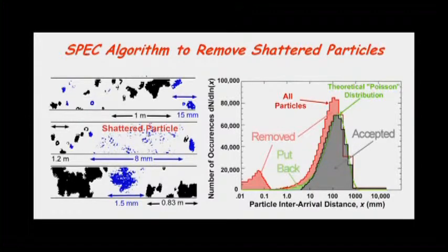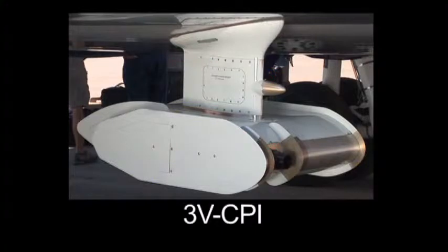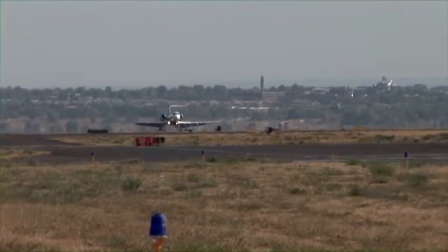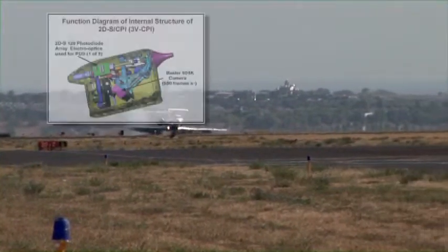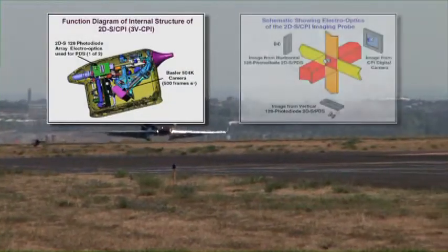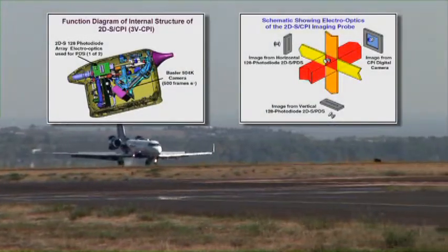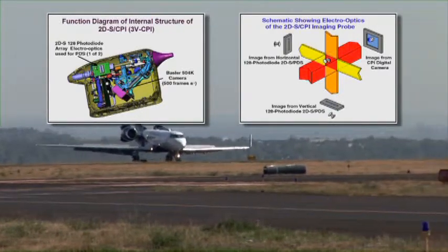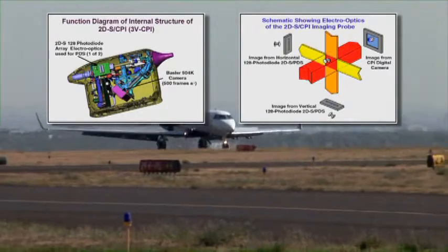All SPEC cloud particle probes also record the arrival time of each individual particle, thereby making it possible to reject closely spaced particles that are the result of ice crystals shattering on the probe tips. The SPEC 3V CPI combines the CPI and 2DS into one cloud particle probe installed on the NCAR G5. The 2DS doubles as the CPI particle detection system and enables the CPI to make quantitative size distributions of both water drops and ice particles in mixed-phase clouds.